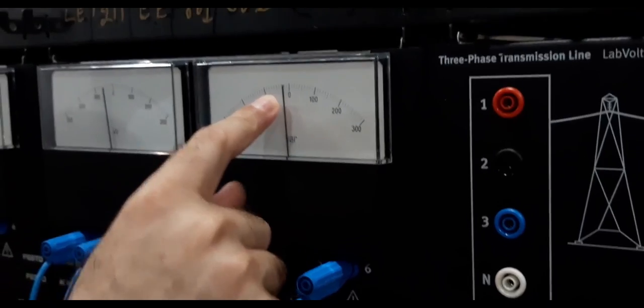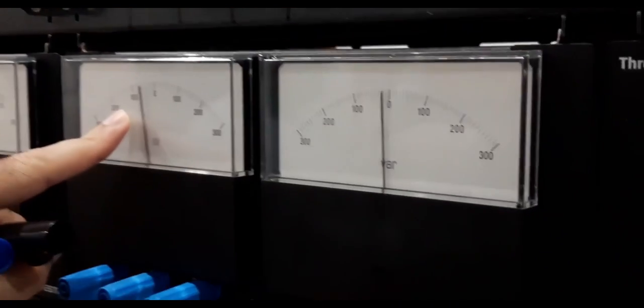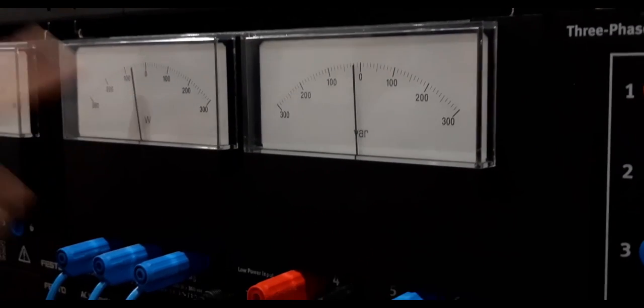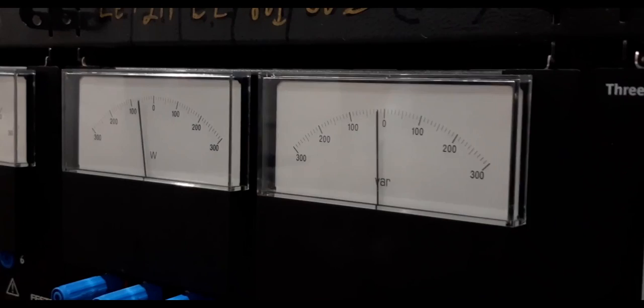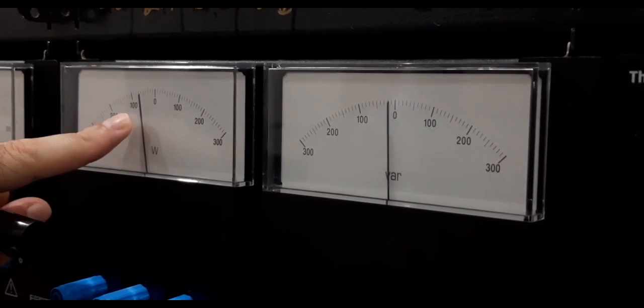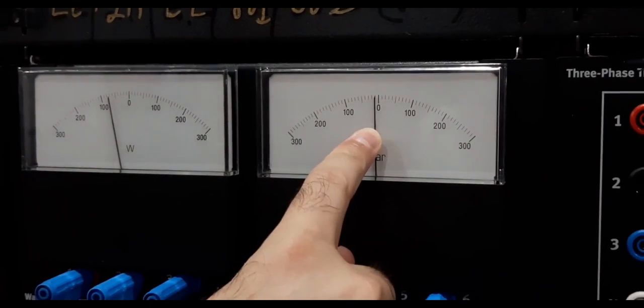The reactive power is more or less the same. It does not change. So now let me further reduce the flux of the DC motor. If the flux reduces, the prime mover power will increase, and you see now the generator provides active power to the system. The reactive power hardly changes.